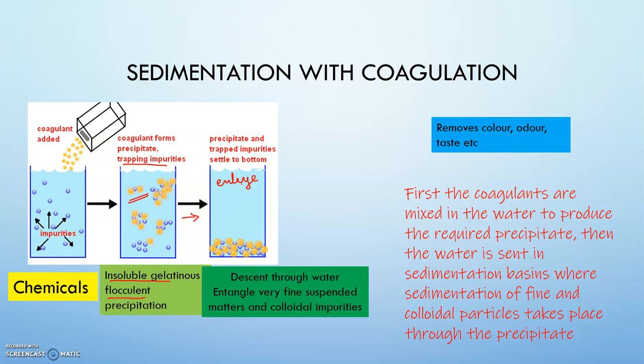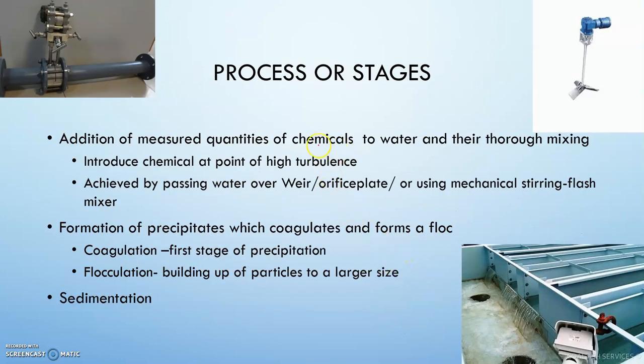The enlargement improves the weight of the floc, so eventually it descends through the water and settles downward along with the impurities. This happens at a much faster rate compared to plain sedimentation. In addition, this process removes color, odor, and taste. It also removes finely divided mineral matter, plankton, animal and vegetative matter, organic coloring matter, and even some bacteria and viruses. The coagulant is added, mixed with water, then it precipitates and settles at the sedimentation basin along with the colloidal particles.